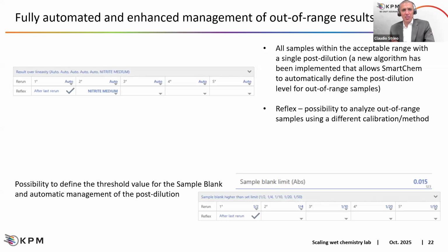We can also automate the management of out-of-range results, concerning those results that are out of range in terms of concentration, where we can define post-dilution or reflex testing. Concerning rerun post-dilution, on our SmartChem a new protocol has been developed that is able to move the out-of-range result back in range in just one shot, by running only one single post-dilution. Because by comparing the absorbance of the sample and the absorbance of the last calibration point, we know how many dilutions we need to perform on the sample to move it more or less to the middle of the range for the calibration of interest. While with reflex testing, we can also decide, instead of running post-dilution, to rerun the sample as it is with another different calibration method.